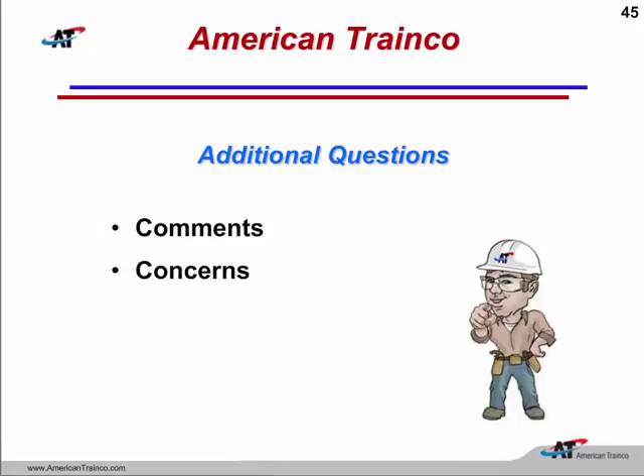With the table method, you don't have to. You just have to say no arc flash PPE required. Protect yourself from shock. I hope that answers that question, because when that question was asked, it's mixing the two methods, and we can't mix those two methods anymore. That is done. And so as we review these labels, if we see that the arc flash PPE category was associated with an incident energy level, we're going to have to replace that label.